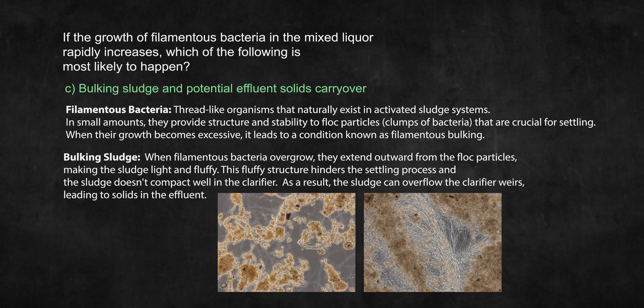The filamentous bacteria will extend outward from the flock, creating a bridging effect between flock particles. This gives the sludge an appearance that can be described as light and fluffy. If the filamentous growth goes unchecked, it can lead to sludge billowing over the weirs of a clarifier, leading to solids in the effluent. Some common countermeasures include increasing wasting, increasing dissolved oxygen within the aeration basin, and continuously dosing the return-activated sludge with chlorine.